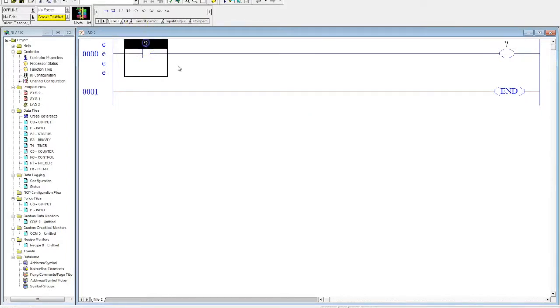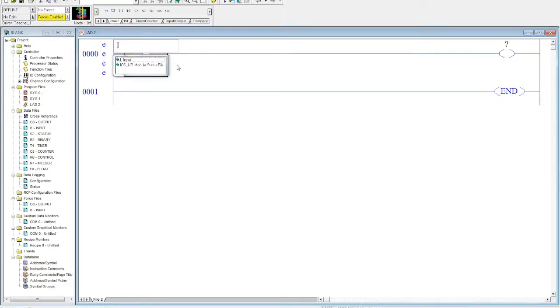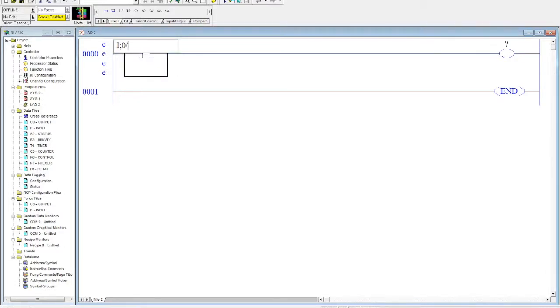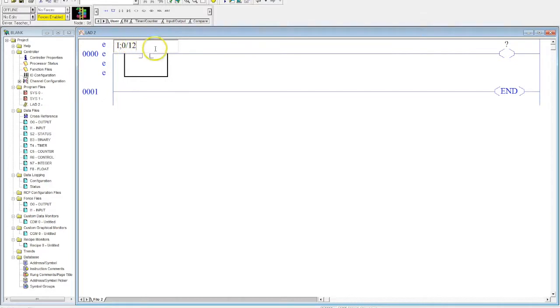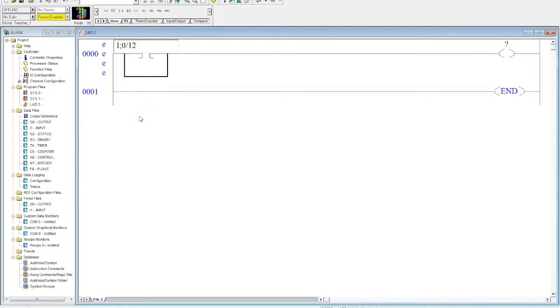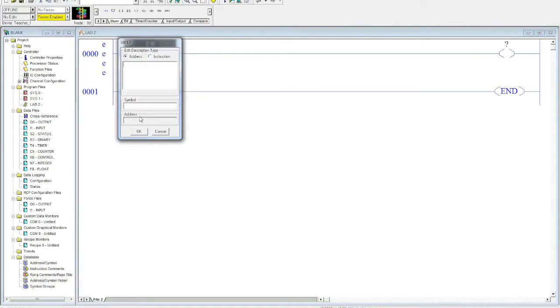So I'm going to address this to one of the known inputs that we established last time. So I'm going to do input, semicolon—don't put a colon in there, put a semicolon—0 forward slash 12. This means that it's an input on slot 0, and it's wired to terminal 12, which was our middle green button. Before I hit enter, I want to talk about why I put a semicolon there. The reason I put a semicolon there is because if I've typed the address in wrong, that semicolon will not change to a colon. But if I've typed it in correctly, it now changes to a colon, and this little screen pops up.